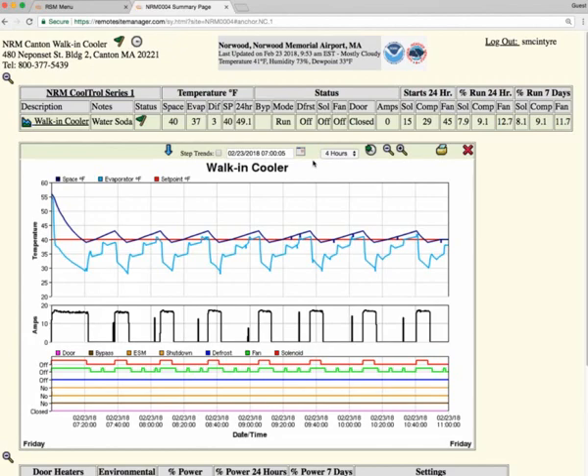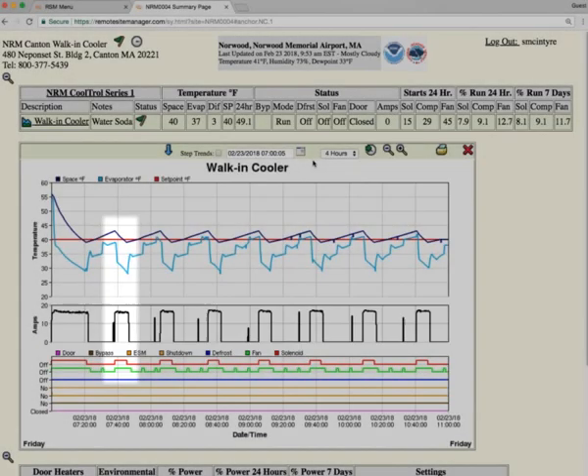So from this graph, you're able to do a little bit of diagnosing. You can see when we call for cooling, you obviously should see the compressor turning on. You should see the evaporator temperature dropping, the room temperature dropping. When it reaches its set point, the refrigeration, we stop the call for cooling, the compressor shuts off, and the fans shut off.